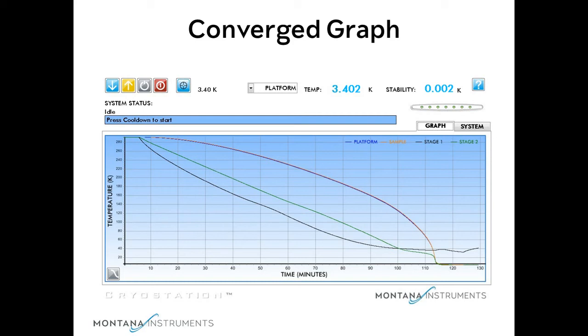Let's put the system in standby so it will hold the temperature there. This keeps the sample at that temperature and reduces power consumption while the experiment proceeds. This is also handy for overnight operation, where the sample chamber can be held cool overnight, so you don't have to wait for complete cool down in the morning.